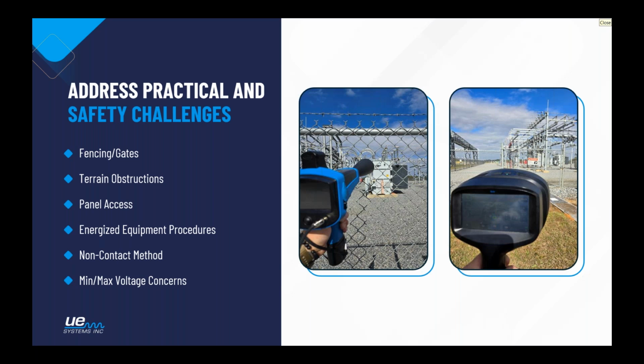Also, because this is a non-contact, non-invasive inspection, that does change our approach, and it usually allows for a lot more flexibility on the inspection of energized equipment. Once again, we're not having to put on necessarily different levels of PPE requirements because we're not making that contact. So that can make the inspection faster and easier, and honestly more comfortable. As I said, it's a non-contact method.